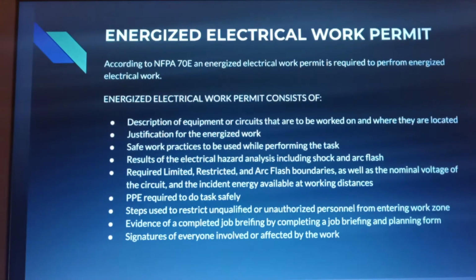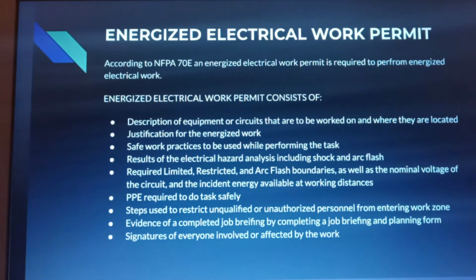Results of an electrical hazard analysis, including shock and arc flash. Required limited, restricted, and arc flash boundaries, as well as the nominal voltages of the circuit and the incident energy available at working distances. And all that stuff we're going to get into later on in this presentation. PPE required to do tasks safely. Steps used to restrict unqualified or unauthorized personnel from entering the work zone. Evidence of a completed job briefing, by completing a job briefing and planning form, and then signatures of everyone involved or affected by the work.